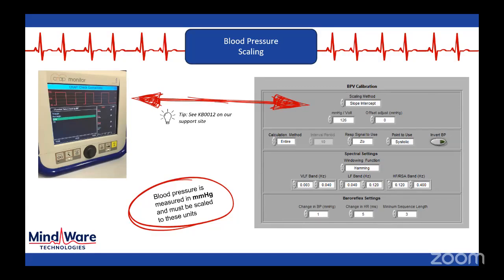With some of these momentary systems, the data is typically going to be stored in its scaled values. So out of those systems, you're going to get measurements in millimeters of mercury, which is the standard unit of measure for blood pressure. And it's going to be in a spreadsheet or in a file somewhere, and we can use those just as they are. But when we're bringing in data through our BioNex, like I depicted earlier on a slide, we do need to tell our system what the scaling is from the voltage that's coming out of that system into ours to millimeters of mercury.